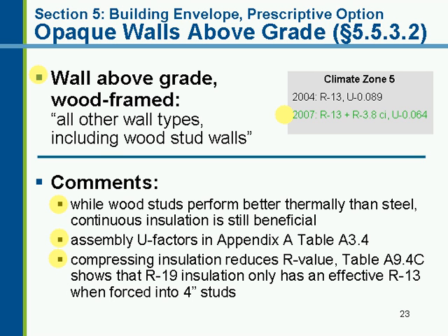So sometimes we see this situation, we see designers or contractors come in, they want to achieve the R19 and they're used to building 2x4 walls and they just figure they'll buy thicker insulation and stick it in the same framing. You end up losing all the additional value. So if you're only going to get R13 in the 4-inch stud, you might as well buy R13 and not buy the R19. If you want the true R19, then it needs to go in the 6-inch stud.